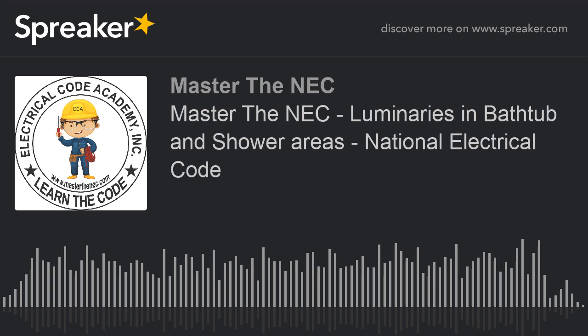Now let's move into the actual shower and tub physical outside dimension spaces, because now we want to talk about what luminaires I could put in there. Number 2 says luminaires located within the actual outside dimensions of the bathtub or shower to a height of 8 feet vertically from the top of the bathtub rim or shower threshold shall be marked suitable for damp locations. So obviously they can be in there. You still can't put the ones prohibited in (D)(1), but you could have a recessed or surface mount luminaire in this location. It has to be damp location rated.